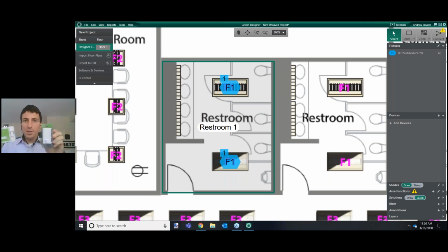The other option is an in-wall device that has the Maestro form factor. Both of these are viable options to control switched lighting here in the restroom. And which one I want depends on a few things, but for the purposes of this example, I'm simply going to choose the PowPak arbitrarily. You may want to choose the in-wall switch if perhaps there's already wires in the wall, if this is a retrofit, but I'll leave that to you for your own project decisions. So I want to use the PowPak.